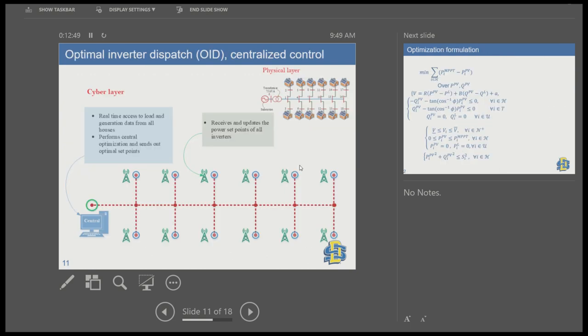The optimal inverter dispatch, or centralized control, uses a communication infrastructure where load data, irradiance data, and all relevant information are sent to a central point. If we have information about load and generation at each node, we can find the optimal dispatch for each inverter and send that information in real time. This central node performs a single optimization and sends out all optimal setpoints to all PV inverters.